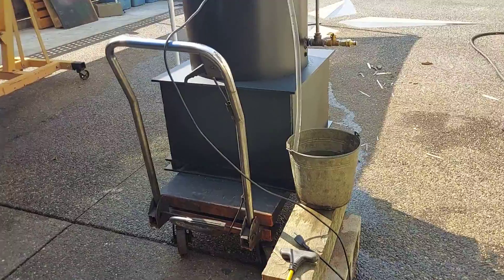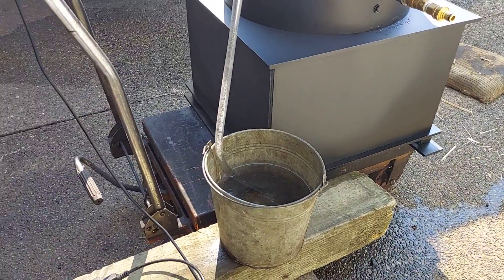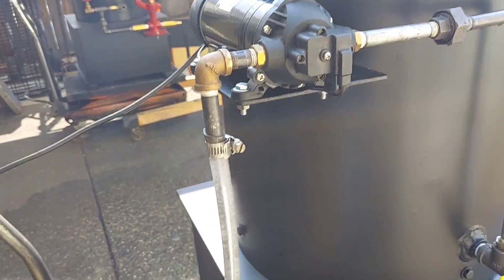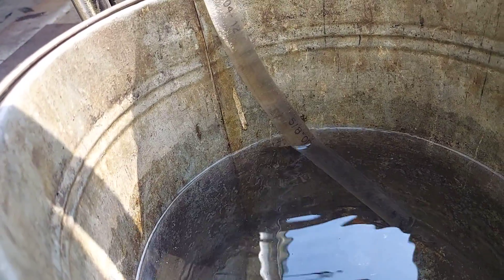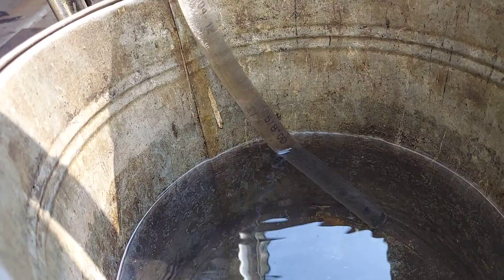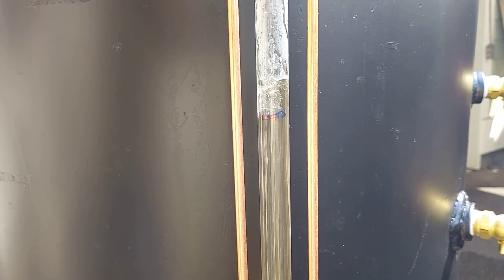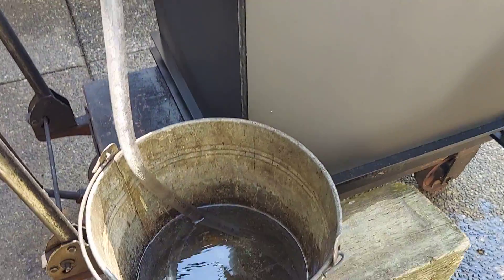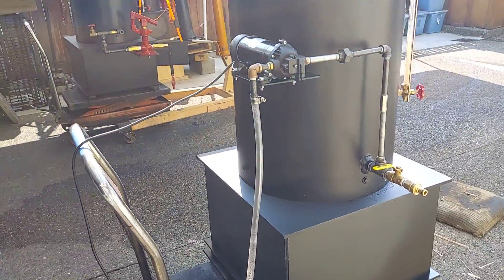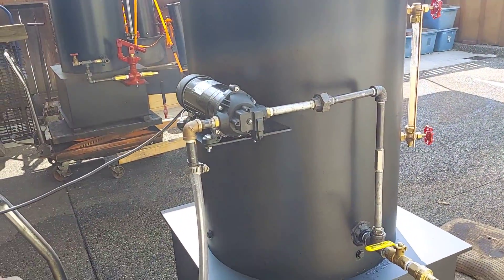So I'm going to pause the video here and plug in the power. It's running now. You can see the water going down in the bucket and the water rising up in the sight glass. It's pumping against 100 pounds of steam pressure — it's rated at 160. You can see how far it's gone down. So I'll be continuing testing this, and this is what I'm going to be using from now on for getting water into the boiler.